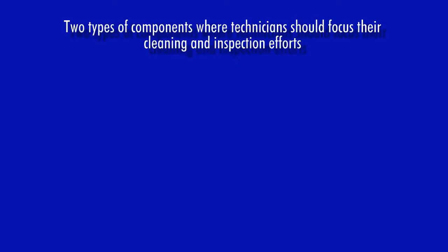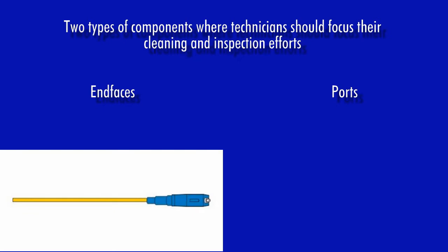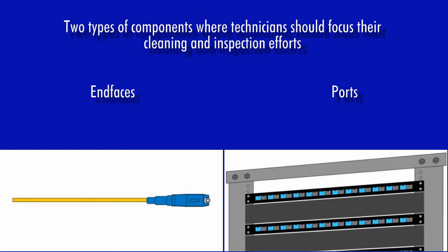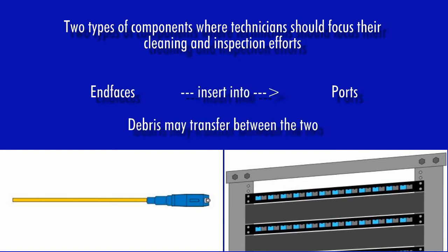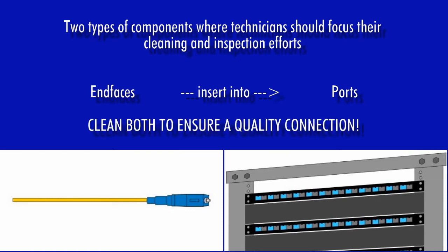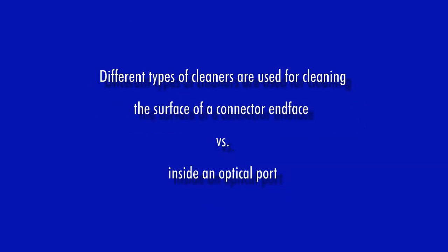There are two types of components where technicians will focus their cleaning and inspection efforts: end faces and ports. An end face is the tip of a fiber connector, while a port is inside a patch panel or equipment port. Connectors insert into ports, so there is a good chance that if one of these components is dirty, debris will transfer onto the other during insertion. Thus, it doesn't help to clean just the connector or just the port. Both need to be cleaned and inspected to ensure a quality connection. However, it should be obvious that a device that can clean a connector end face would not be able to clean inside a port.